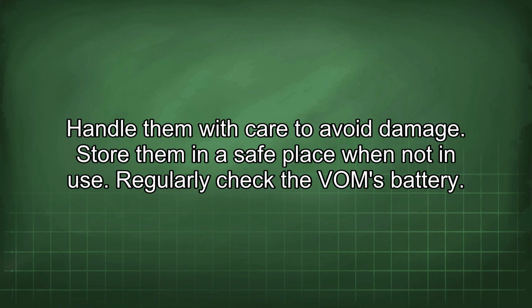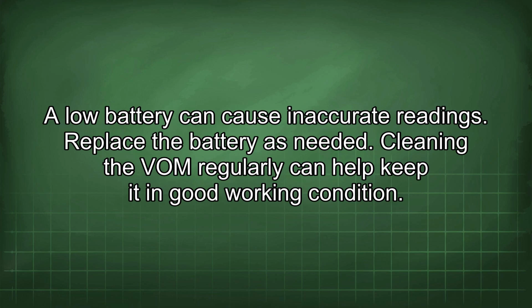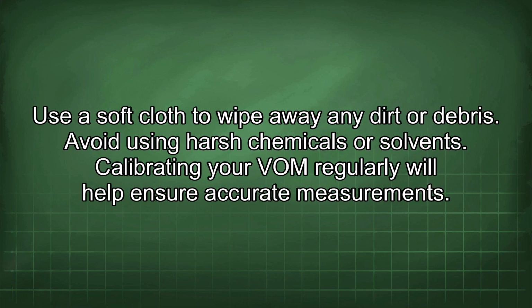Regularly check the VOM battery. A low battery can cause inaccurate readings. Replace the battery as needed. Cleaning the VOM regularly can help keep it in good working condition. Use a soft cloth to wipe away any dirt or debris. Avoid using harsh chemicals or solvents.